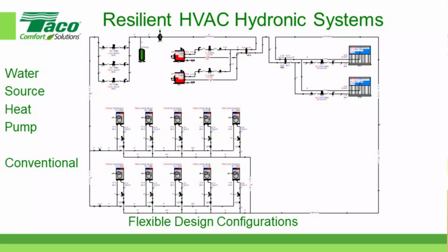This first one here is very popular for hydronic systems: a water source heat pump. Each one of these has a water supply. In this case, water is circulated through primary pumps over here through the water source heat pump. This could be, for example, a very simple two-story building that has 5 zones per floor. Then we can inject heat through a boiler system, maybe burning natural gas, and inject that into the loop.